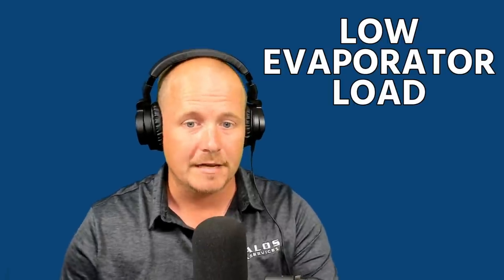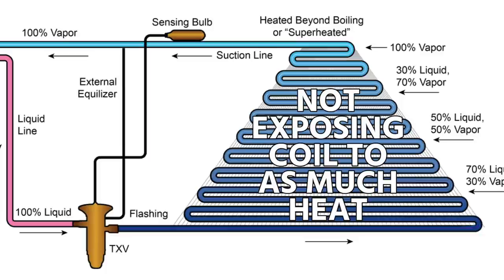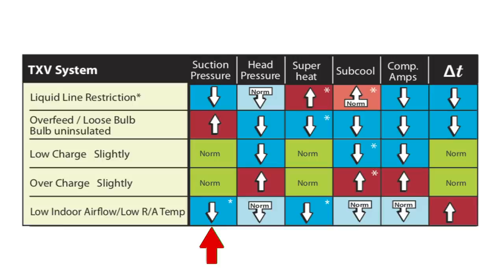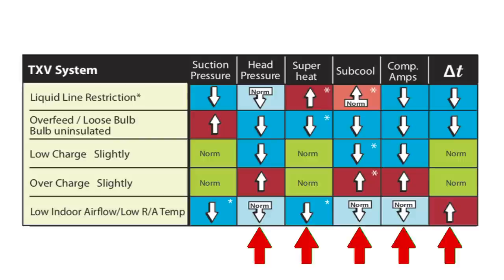Low evaporator load means you're not exposing that evaporator coil to as much heat, generally due to low airflow moving over that indoor coil. You're going to see low suction pressure, low to normal head pressure, low superheat, low to normal subcool, low compressor amps, and high delta T. Those are your primary indications of low indoor airflow. Hopefully you found this helpful — there's more coming in this series, so stay tuned.